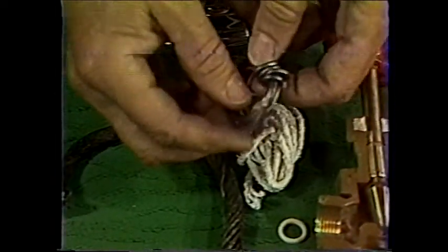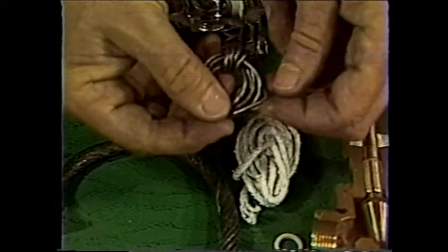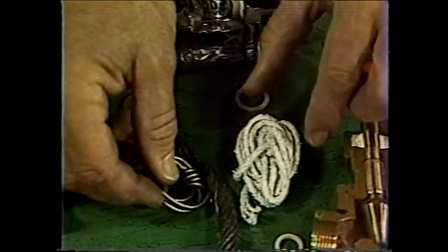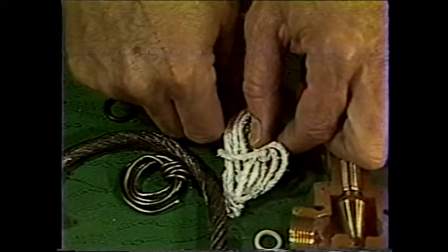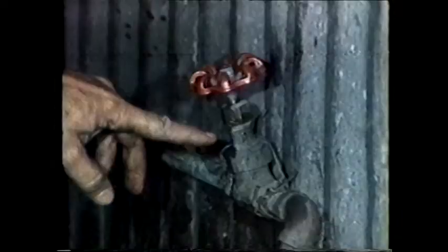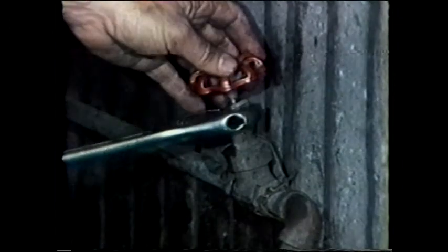Graphite is a form of carbon and is a dry lubricant. Another common stem packing is Teflon, which may be either molded to fit the stem or in string form. One of the chief advantages of a stuffing box is that if it starts leaking, simply tightening down on the packing gland will usually stop it.